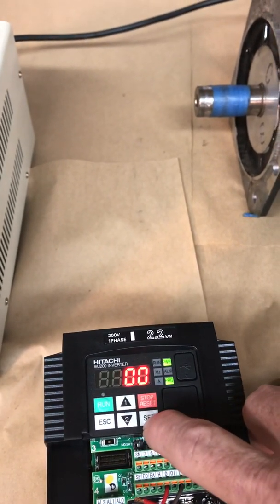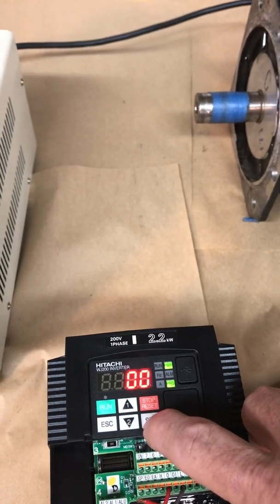Zero three on the Hitachi WJ200 is the sensorless vector. We go to zero, that's the factory default setting which is constant torque. We'll hit set, that's entered.